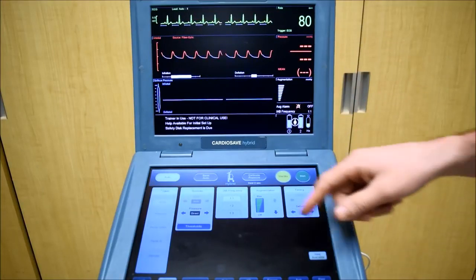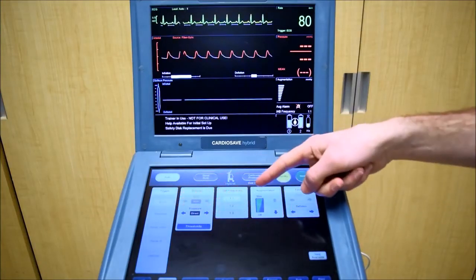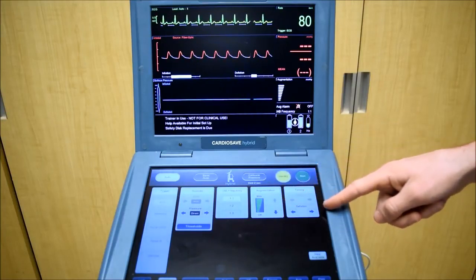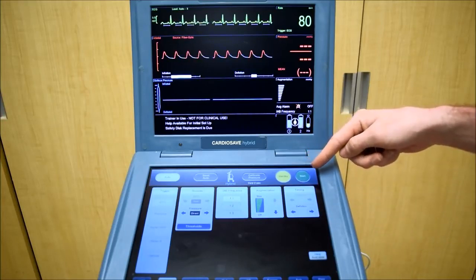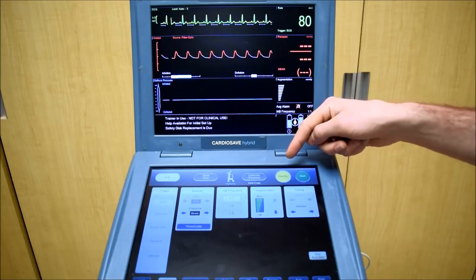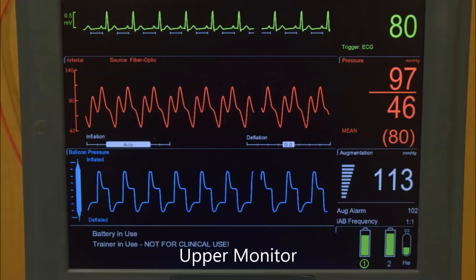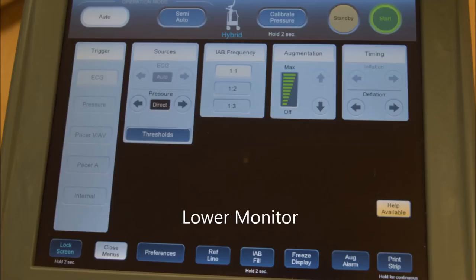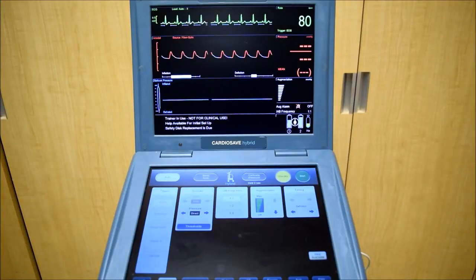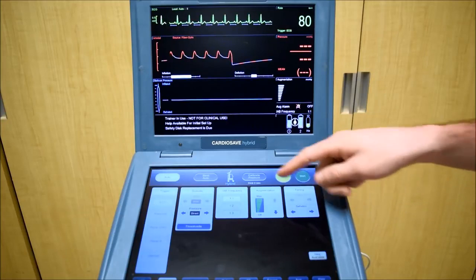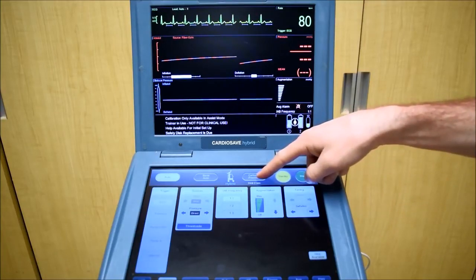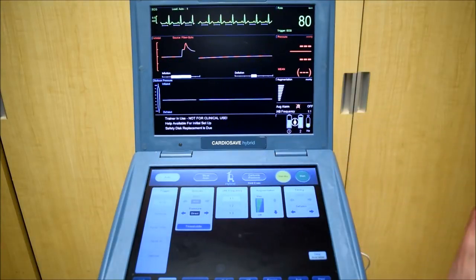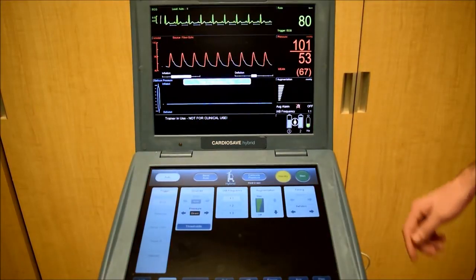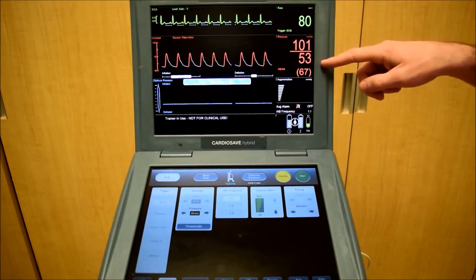In the lower screen, we can control our trigger source, our balloon frequency, augmentation, and timing here. You can start the balloon by pressing this button here and stand by to pause it. Okay, I'm going to quickly calibrate our pressure transducer. So we want to open that to atmospheric pressure and press and hold this calibration button. Okay, now that the pressure transducer is zeroed, you can see our systolic and diastolic and mean pressures here.